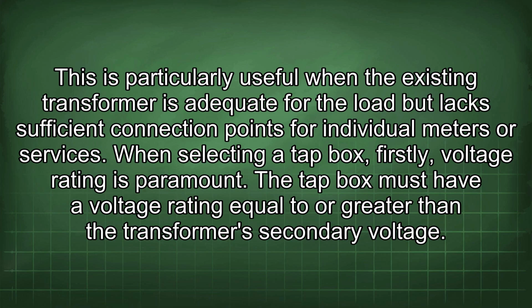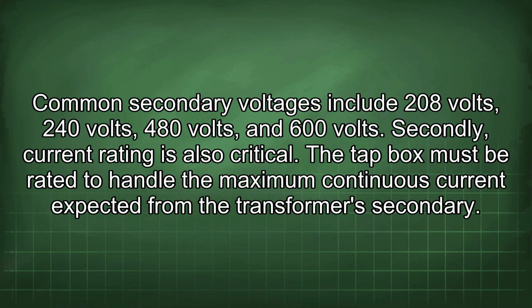This is particularly useful when the existing transformer is adequate for the load but lacks sufficient connection points for individual meters or services. When selecting a tap box, firstly, voltage rating is paramount. The tap box must have a voltage rating equal to or greater than the transformer's secondary voltage. Common secondary voltages include 208 volts, 240 volts, 480 volts, and 600 volts.